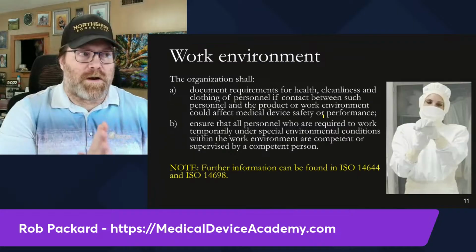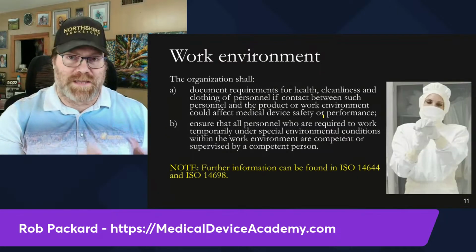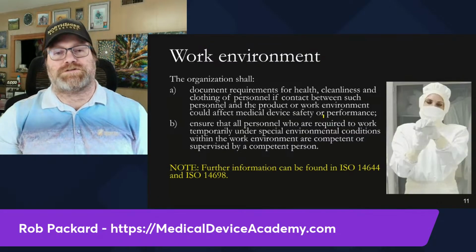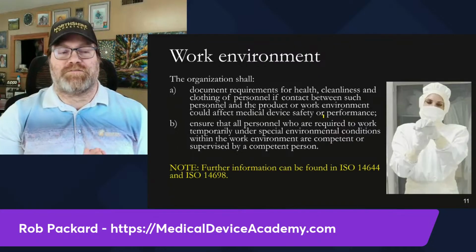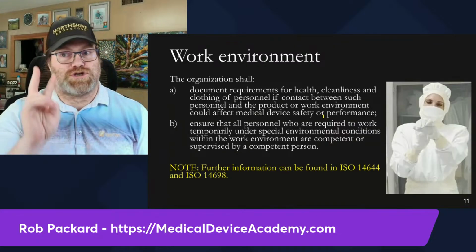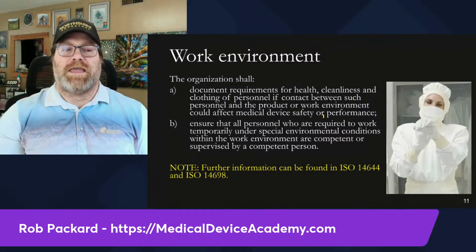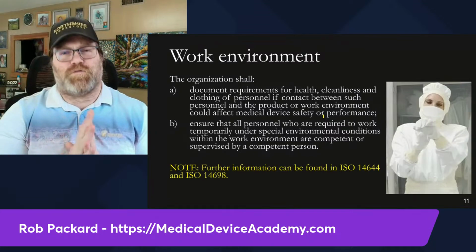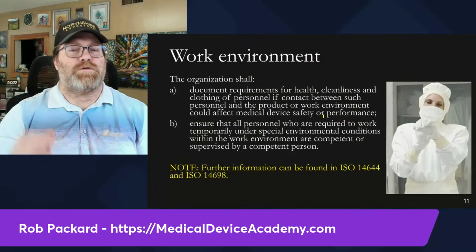There are additional requirements here for the work environment. You can also look at the two standards for the work environment that are referenced as a note in 13485. That is a little bit misleading because 14698 is actually two standards. It's a -1 and a -2. So you need both of those. And 14644, joy of joys, I believe that's up to 14 parts now, but maybe one of them is still in draft. So, or standards.